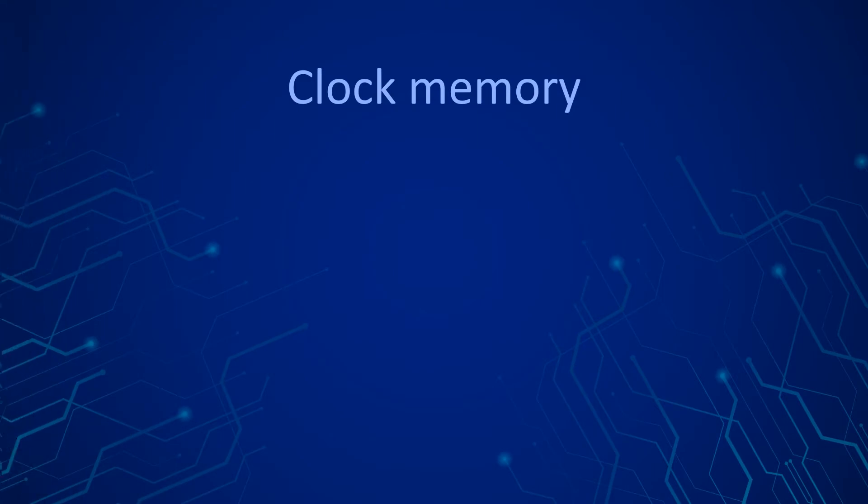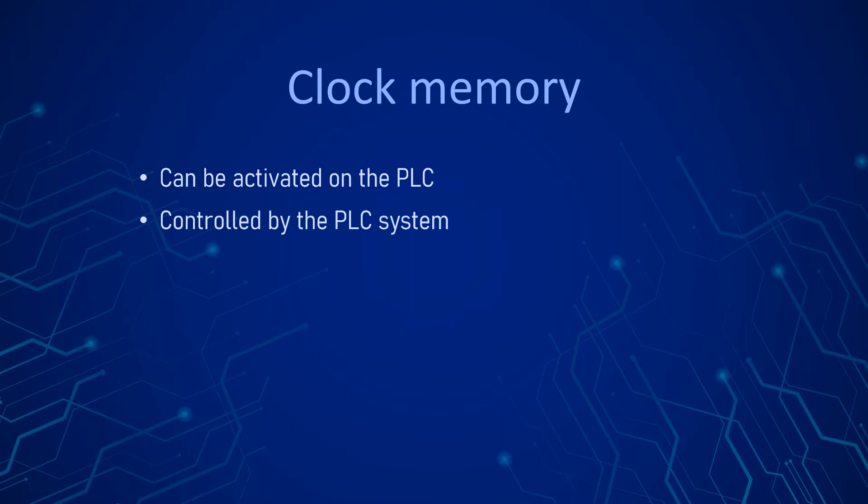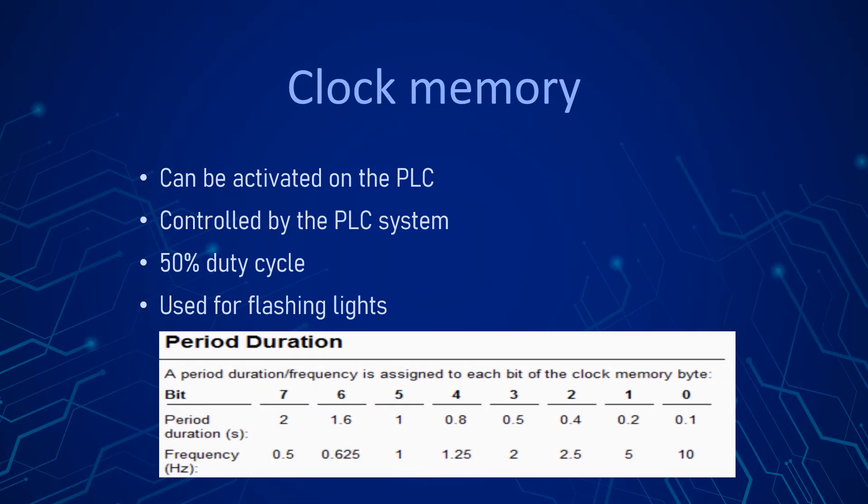The clock memory is a byte, and the bits of it are alternating with given frequency. They are used for example to control flashing lights. We have to enable it by selecting a byte from the memory field. When enabling this function, TIA Portal automatically creates the corresponding tags. The duty cycle is 50%, and the frequency of the alternation are controlled by the PLC system.